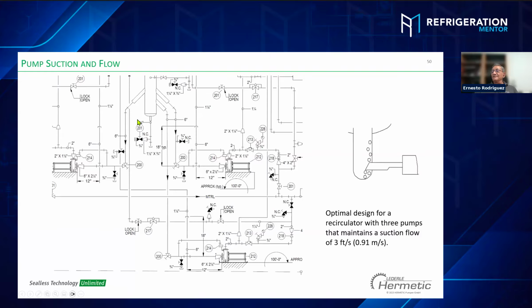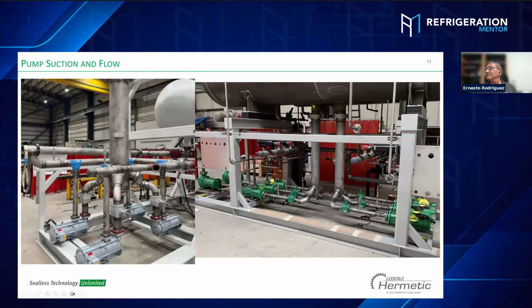This is the typical piping for a pump. For example, to keep the velocity, we have two pumps running in parallel and one standby, and we need to keep this rule of thumb of 3 feet per second. This is typical. This is for CO2, and you see it's in stainless steel. We have a valve box right here, and we keep the distance between the valve and the flange of the pump at a minimum of 5 times the pipe diameter. The same way for multiple pumps, we have these 4 pumps. This is the typical way to do that.